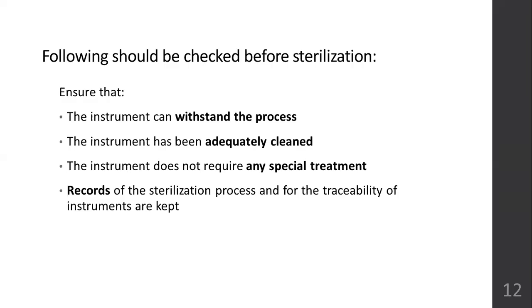You have to ensure that the instrument can withstand the process of sterilization, that the instrument has been adequately cleaned, and that it does not require any special treatment. And each and every sterilization cycle should be recorded. Because if after the sterilization you find that it was not adequately sterilized, those instruments can be called back.